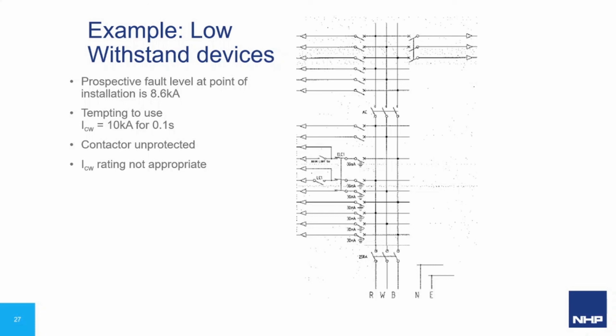The next example includes a low withstand device, and we'll see if you can spot it. The prospective fault level at the point of the installation is 8.6 kA. This may seem quite simple, and at first glance, it is tempting to use an ICW rating of, let's say, 10 kA for 0.1 second. What you may have missed is the load shed contactor. Without upstream protection, contactors have a very low withstand, definitely lower than 10 kA for 0.1 second. So, if ICW rating is not appropriate, let's have a look at what our options are.